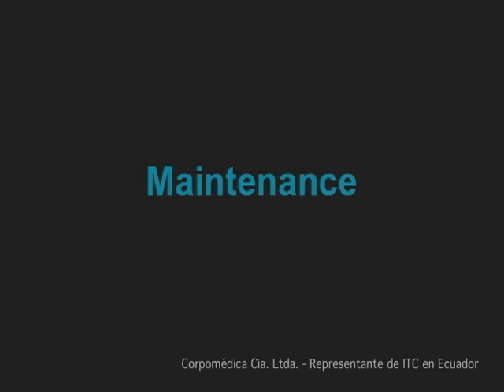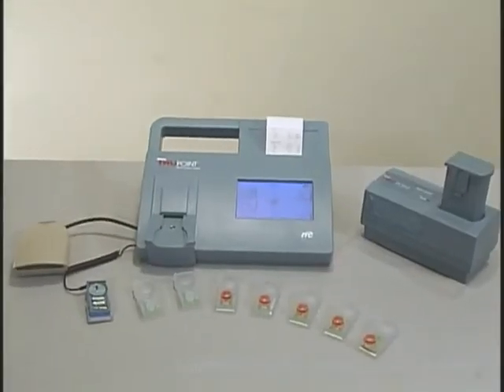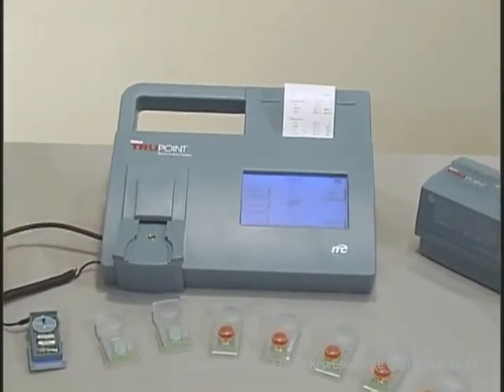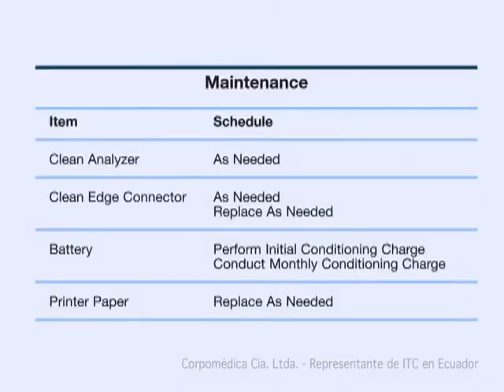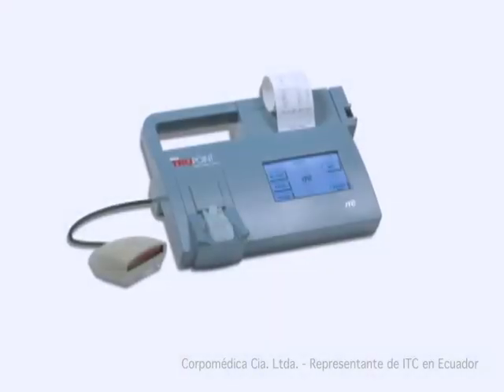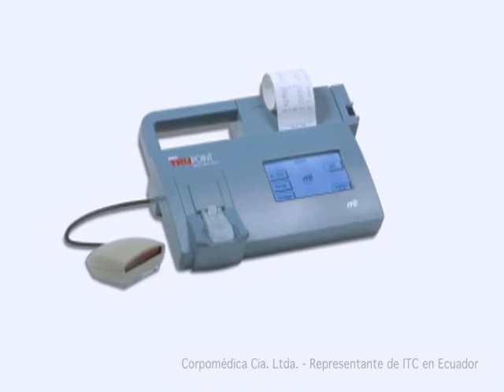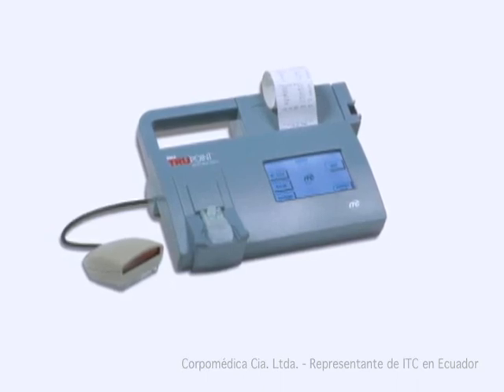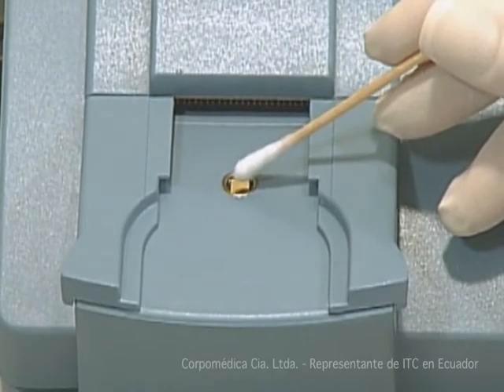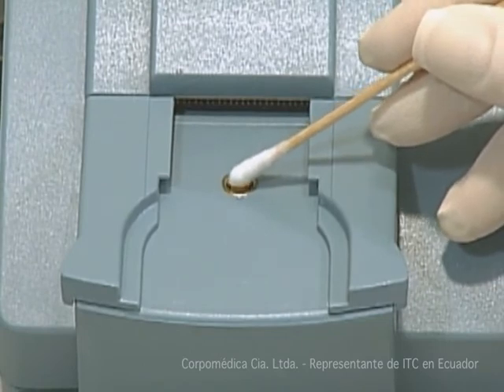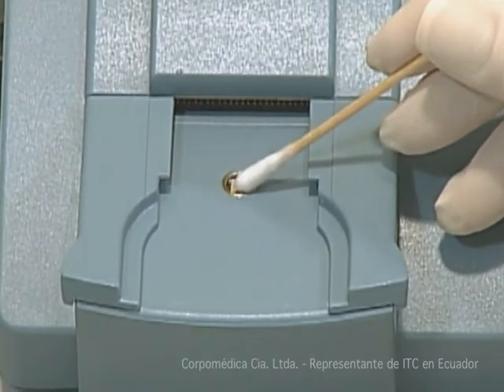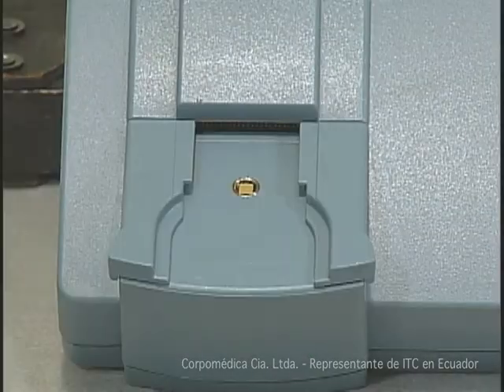IRMA TruPoint analyzers are virtually maintenance-free. To keep your IRMA TruPoint running smoothly, refer to the Maintenance section in the User's Manual. Clean the analyzer surface as needed with isopropyl alcohol, a 10% bleach solution, or distilled water. Do not use bleach on the screen. If the IR probe is dirty or contaminated, clean it with isopropyl alcohol or a 10% bleach solution.